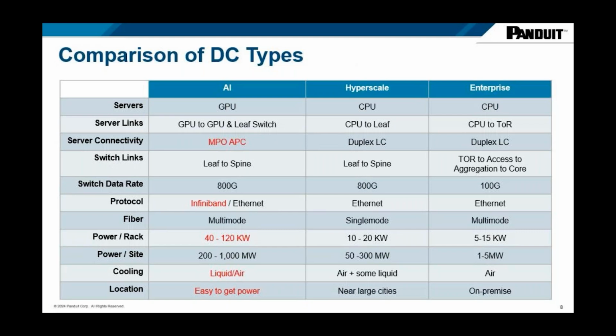We'll move down to power and rack considerations. GPUs are power hungry, and a 100 kilowatt cabinet is not unheard of in AI applications. In the enterprise space, 5 to 15 kilowatts is usually the average, but if you move over to the AI marketplace, we're seeing upwards of over 100 kilowatts per cabinet.